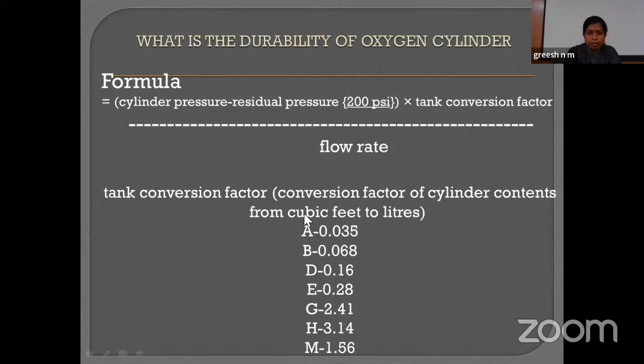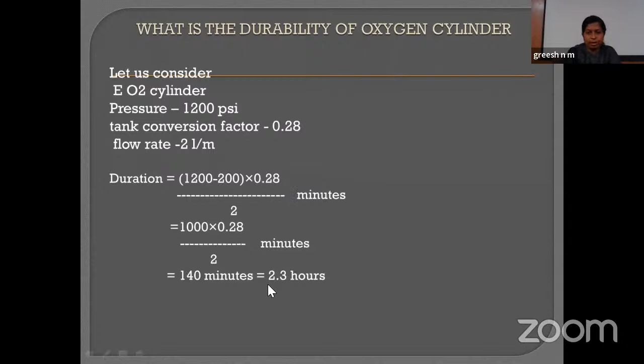So now let us consider an E oxygen cylinder, which has a pressure of around 1200 psi. The tank conversion factor is 0.28, and the flow rate used for the patient is around 2 liters per minute. So the duration of this oxygen cylinder is as follows: 1200 minus 200, into 0.28, divided by 2. So this gives approximately 140 minutes, that is equal to 2.3 hours.